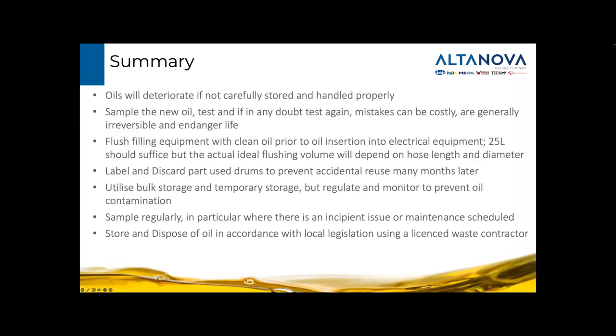So to summarise, oils are specialist products. They need to be handled with care to retain their chemical, physical and electrical properties. Take samples at every opportunity. If in doubt, sample and test again. Mistakes are usually irreversible and they may even endanger life. Ensure any apparatus you use to take samples or fill equipment with is adequately clean and flushed prior to use. Take into account the size of pipework to calculate the most appropriate flushing volume.